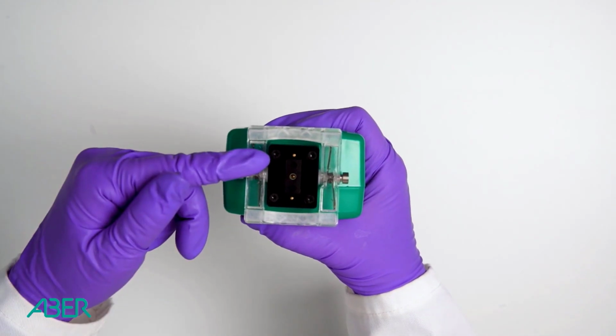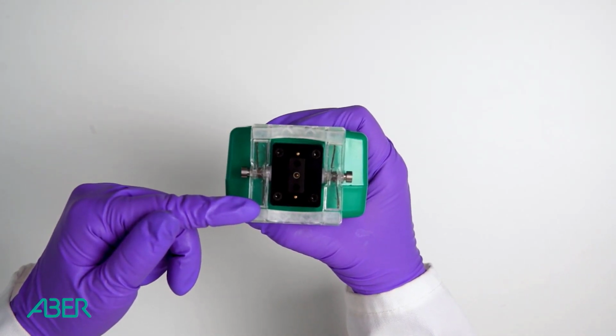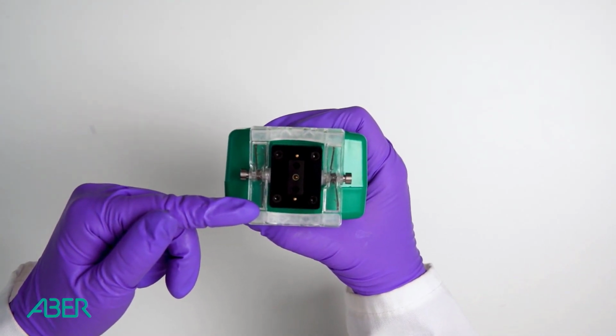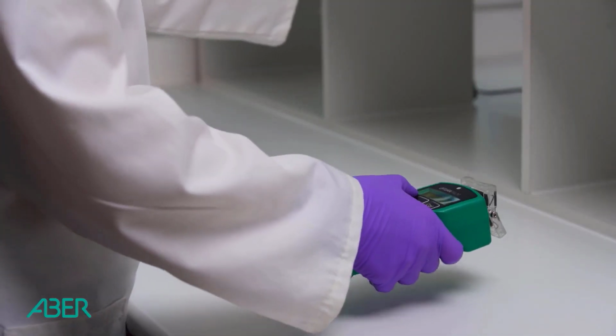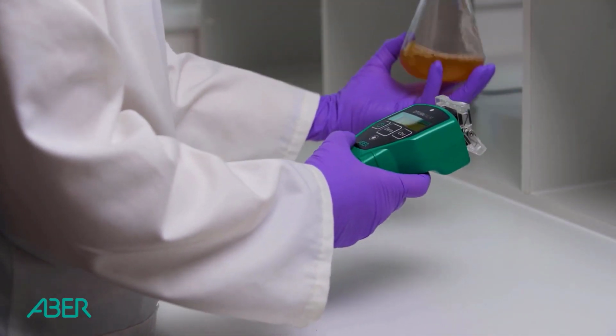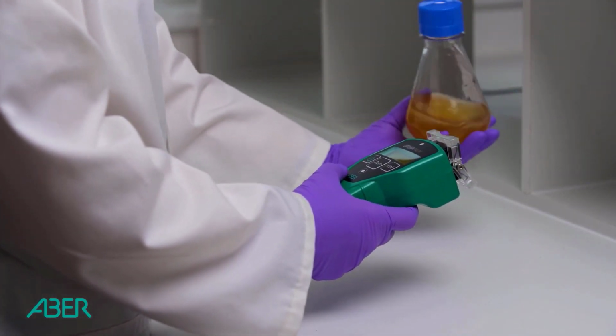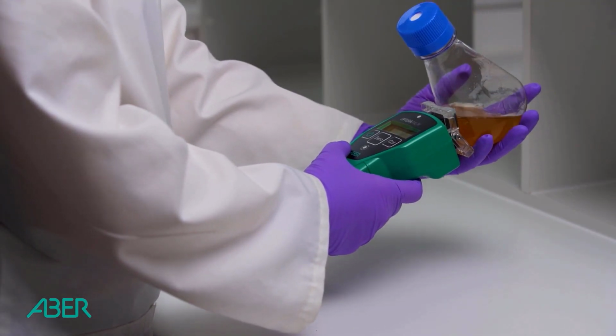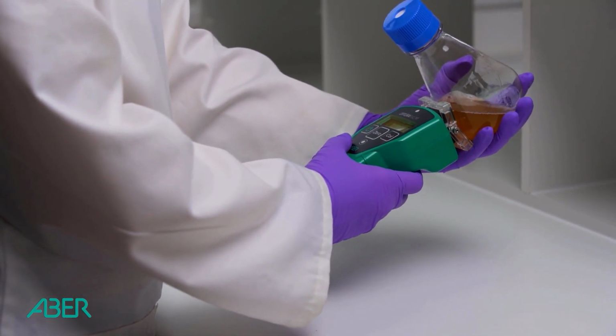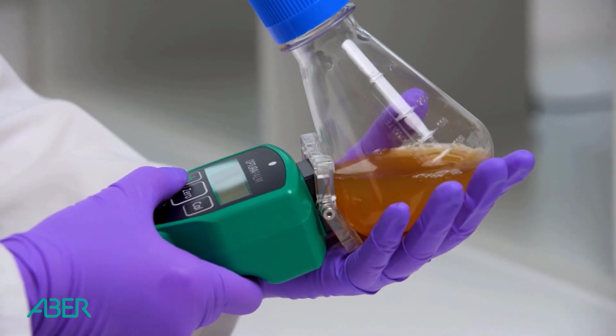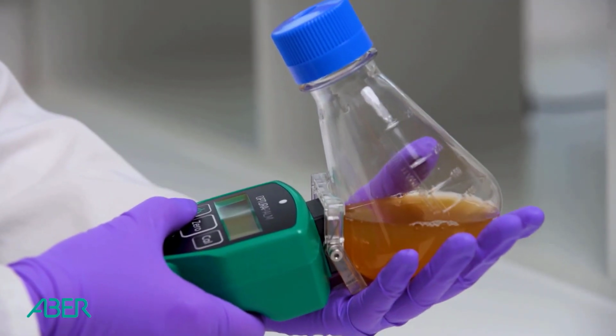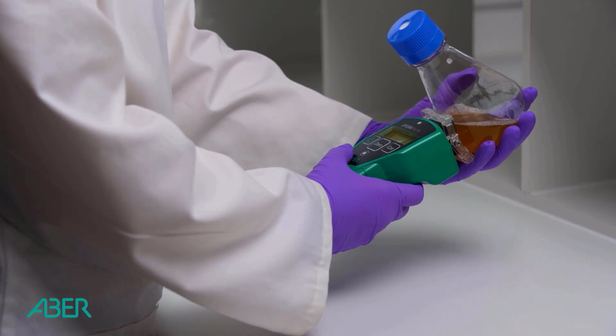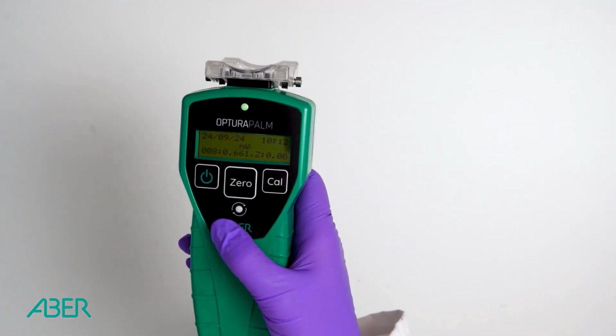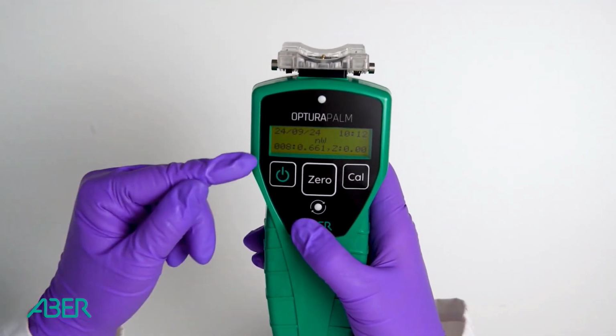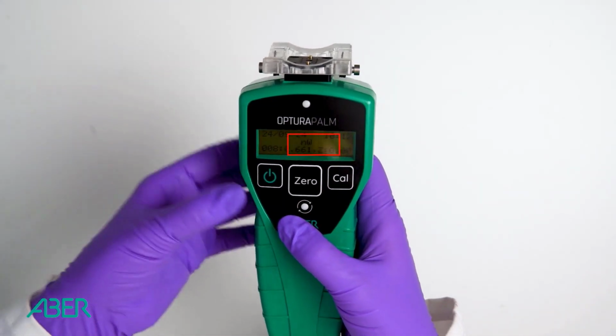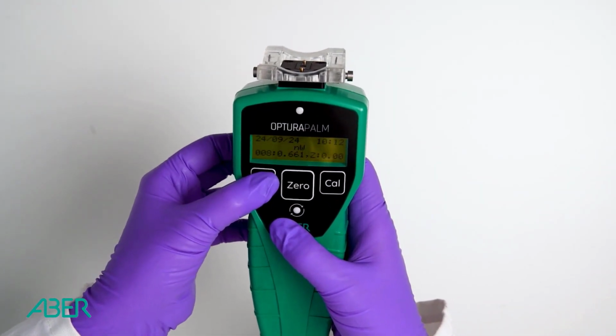The palm measurement is initiated when the two pins present on the measurement face are both engaged against a rigid vessel wall. Ensure that the flask is clean and the cells are in suspension. You may need to tip the vessel to ensure that there is enough liquid in front of the sensor. This should be around 2.5 centimeters. Simply press the palm against the vessel, hold the palm and flask still for 5 to 7 seconds, and your readings will be complete. Your measurement will appear at the bottom of the screen next to the measurement number. 1000 readings can be stored at any time.